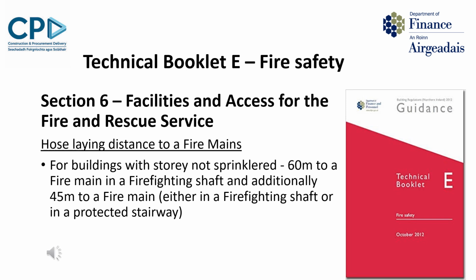There is a change in the guidance that relates to the hose line distance from anywhere on a floor to a fire main. For buildings with stories not fitted with sprinklers, a new additional criteria has to be met for buildings requiring firefighting shaft provision. So previously in TBE for these buildings, the sole criteria was that each part of the floor was to be within 60 metres of a fire main in a firefighting shaft. This requirement continues to apply.